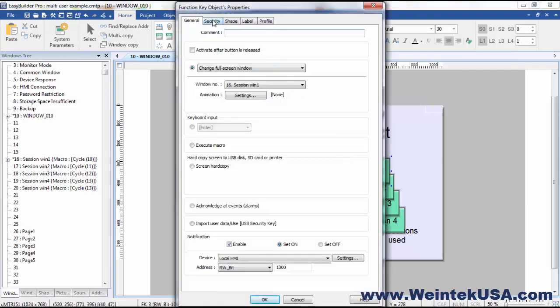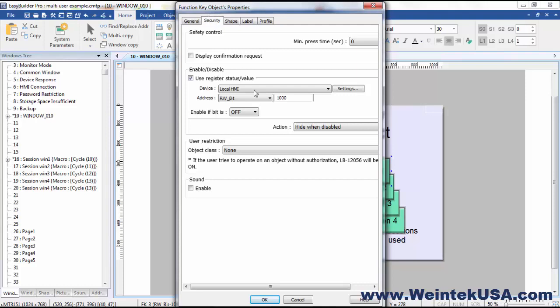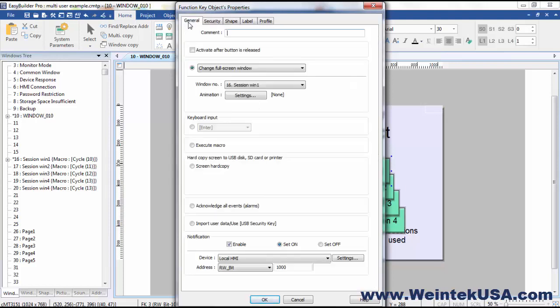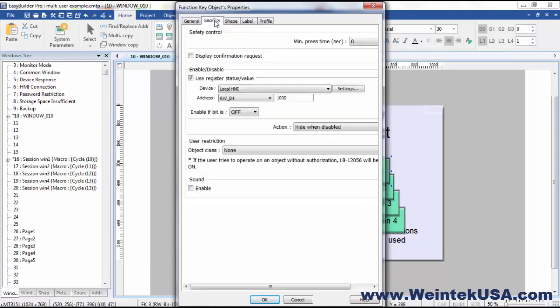From the security tab, you can see that this function key is only enabled if rwbit 100.0 is off. So back over on the general key, we add a notification bit, which is the same bit, 100.0, and we set it on. So as soon as we hit the navigation key, we disable it. And under the security settings, we've got it set to hide when disabled.